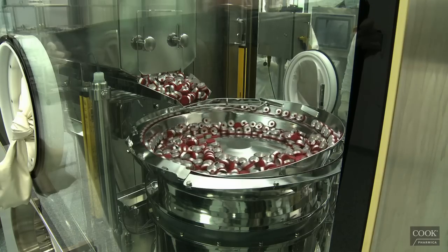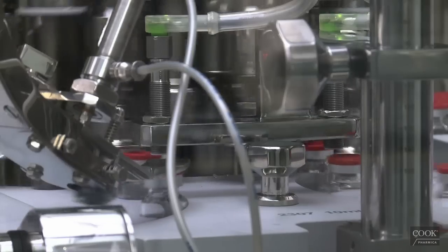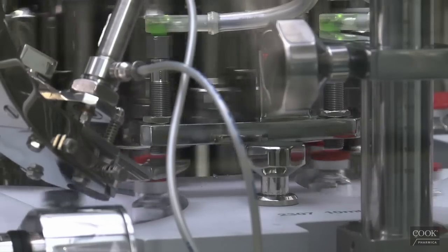Sterile caps are charged through a rapid transfer port and are crimped using a rotary-style crimping wheel with adjustable head pressure and spin speed. The capping operations are all performed under barrier isolation.